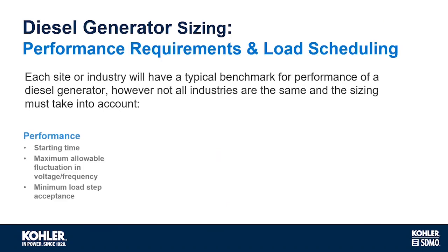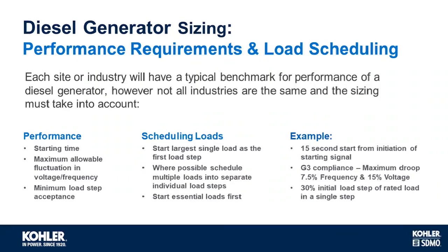Each site or industry will have a typical benchmark for performance of the diesel generator. However, not all industries are the same, and the sizing must take that into account. So performance: the start time, the maximum allowable voltage and frequency drop, the minimum load acceptance, how those loads are scheduled. So our advice would be to apply the largest single load step first. Where possible, schedule multiple loads into separate individual load steps, but also keep in mind that you may need to start essential loads first. So a simple example: a 15 second start from initiation of the start signal, G3 compliance with a maximum droop of 7.5% on frequency and minus 15% on voltage, and an initial load step of say 30%.